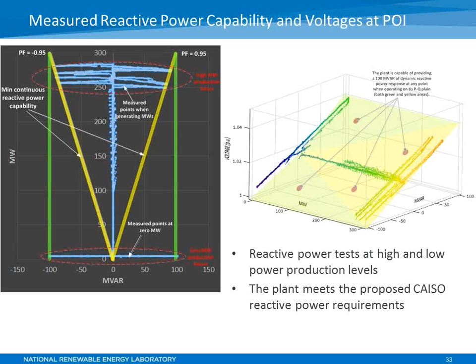especially at the zero power levels, because this is somewhat a replica of nighttime operation of a PV plant when there is no solar resource available, but it still can provide reliability services to the grid. So the plant was tested to demonstrate the control operation also in other modes, which I will get to in a second. But the 3D graph on the right is basically a more articulate view of the same test, with voltage on a 230 kilovolt line also shown on the vertical axis to show that it's also being impacted during this test.